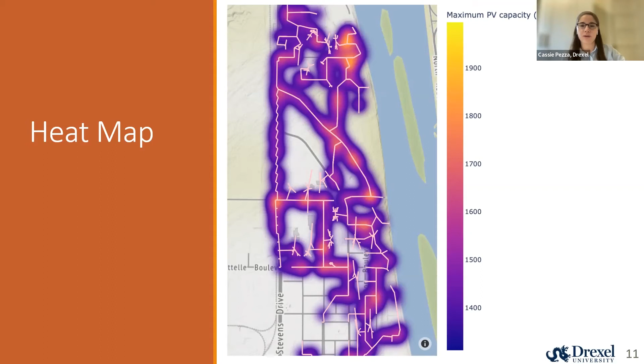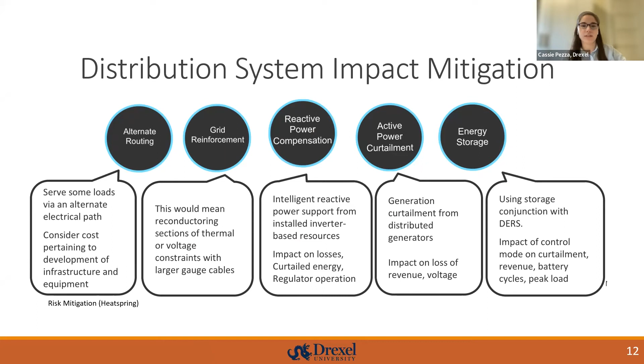So you can do alternate routing where you're not connected to the same transformer or same wiring. You can reinforce the grid so that way you're either upgrading the gauge of the wire or you're upgrading your transformers so they can host more PV. There's also reactive power and active power curtailment, so that way you're limiting how much you're actually exporting. These options aren't the best because basically they have negative impacts on your loss. And then you can also utilize energy storage to limit how much you're exporting to the grid. In our case, that would be the best route because we are already designing a system with storage for the resiliency of the system.